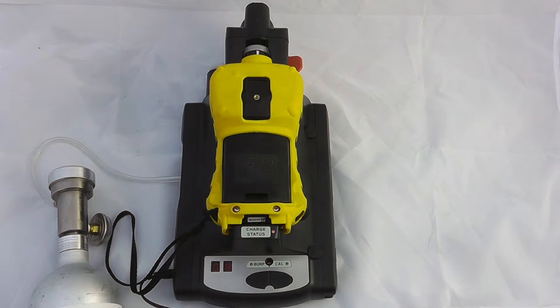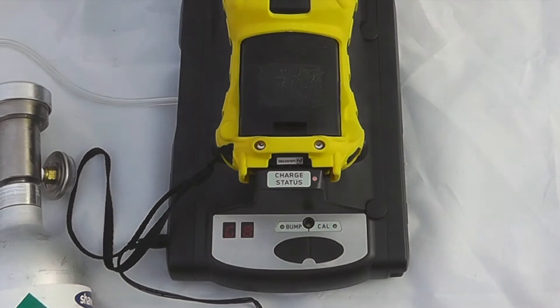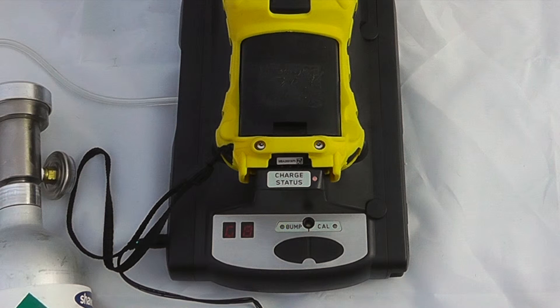If the light goes green at the end of it we know it's been a successful bump test and if it goes to red it will either automatically go into a calibration cycle or you'll have to manually calibrate the device. So we can see that that bump test has been successful.